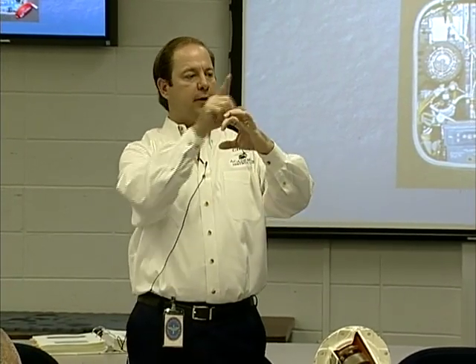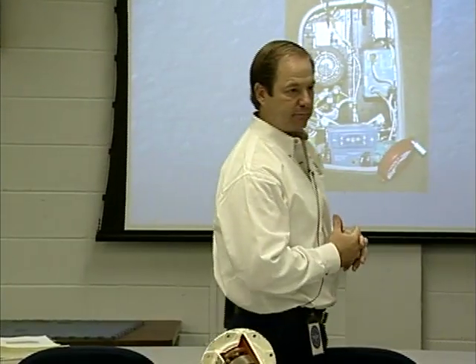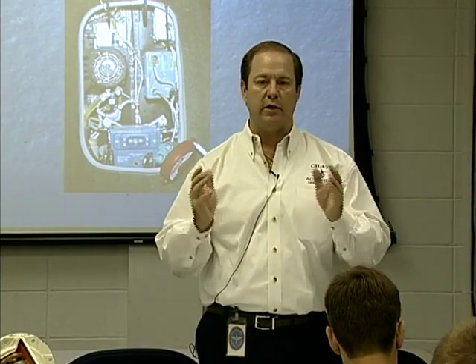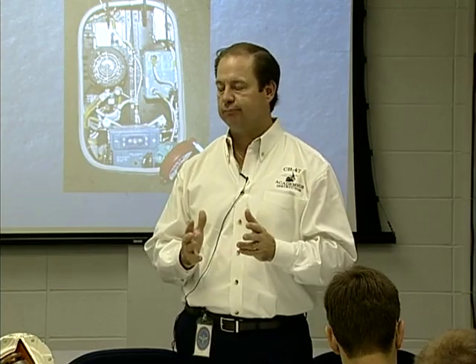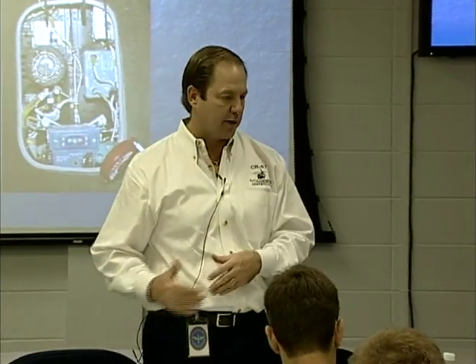What is now going to happen is through that relay, it's going to send power backwards through that battery, causing a chemical reaction that results in charging it. Now what's the benefit of that system versus the one we got rid of? With that system, there's no possible way to overcharge the battery. It can only take it to the max capacity it can take. Once you put a battery in brand new, chances are it never recharges all the way up again. That's why I'm careful to say it'll charge back up as far as it can, but it cannot exceed it.